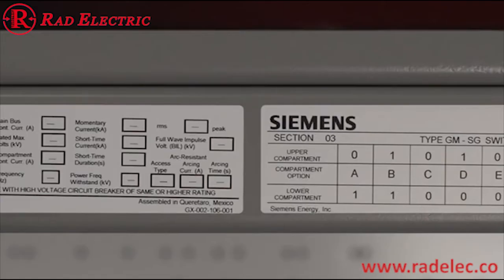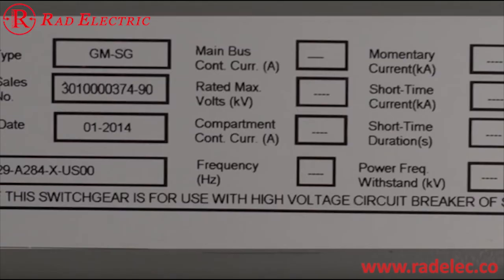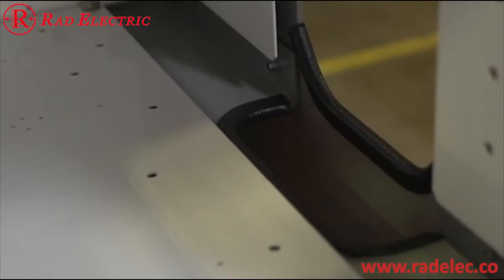The second label is the UR Component Recognition label. It details what section of the equipment was manufactured in the Siemens factory, so the rest of the equipment from our OEM partner can be certified. When feeding wires in and out of the low voltage compartment, you'll notice the spaces are lined with edge protectors. This prevents the sharp metal edges from destroying the insulation on the wires.